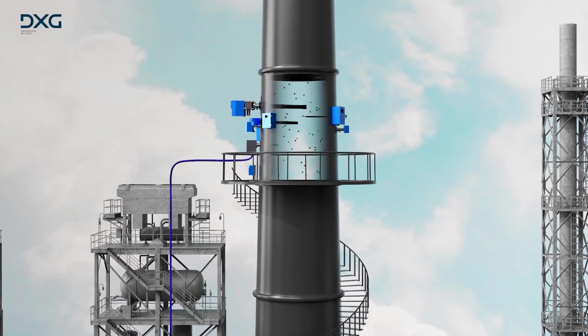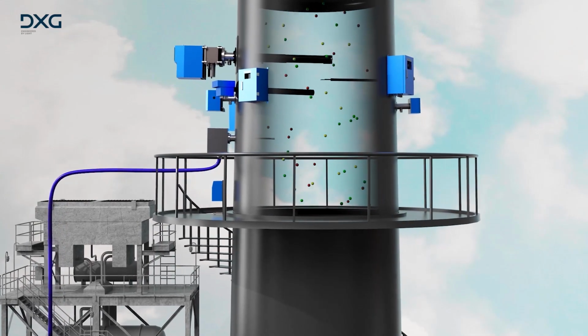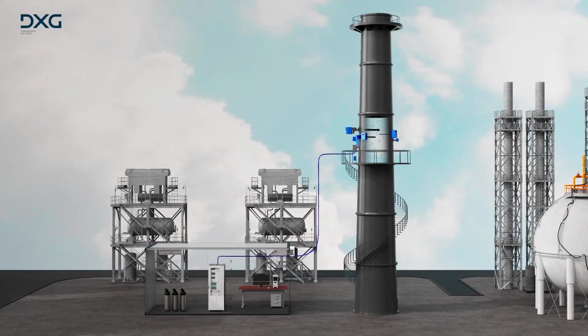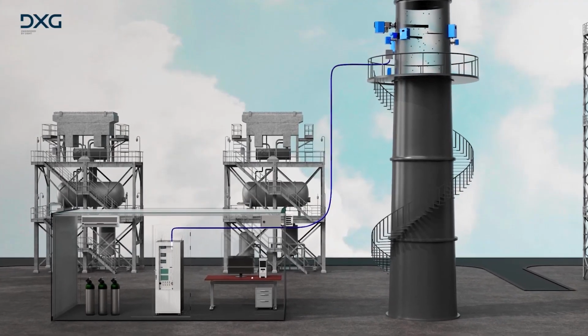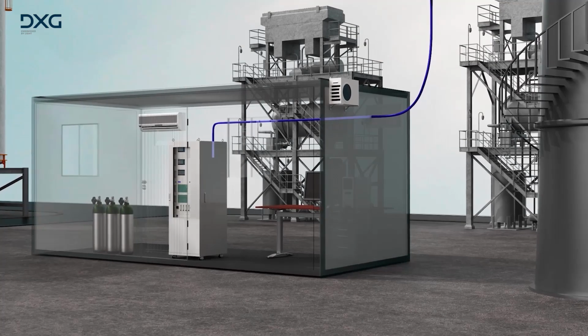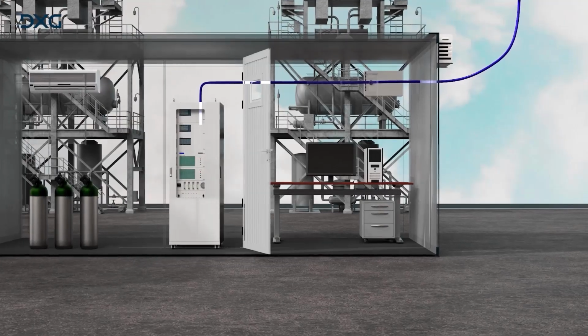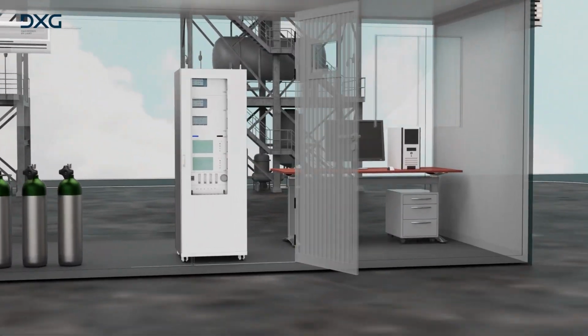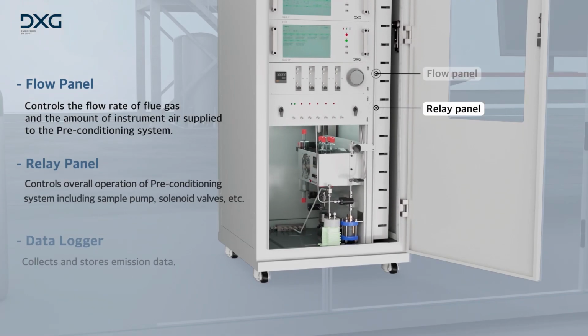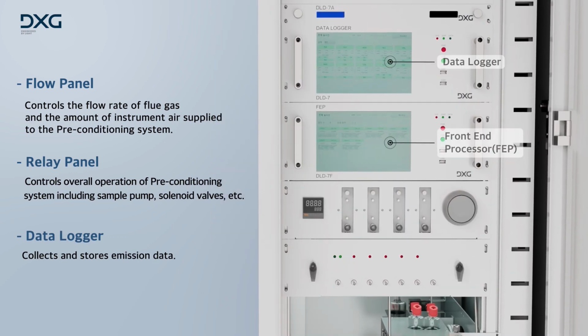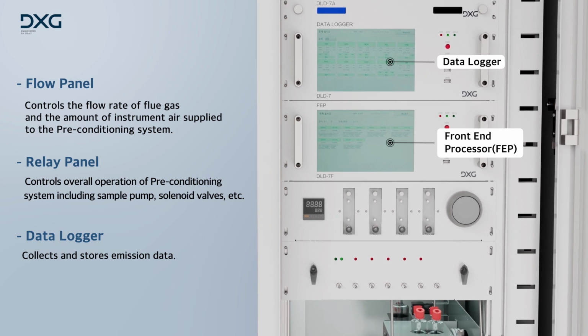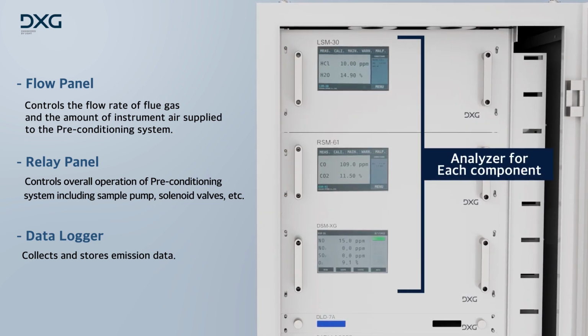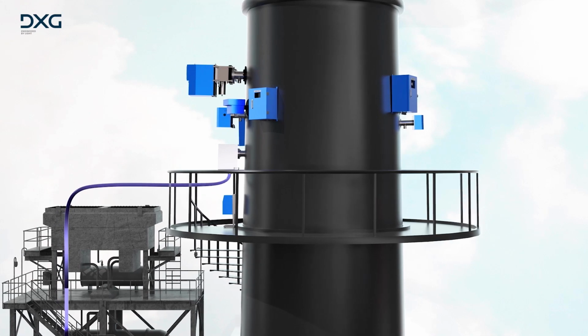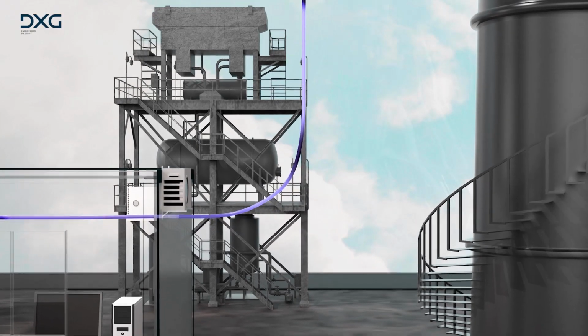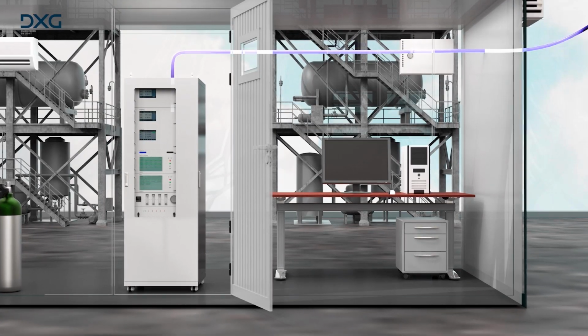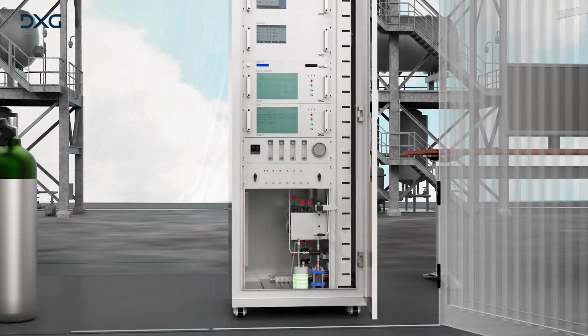In the Extractive type, also referred to as the sampling type, a sample probe and a sample pump are used to extract a gas sample from inside a chimney, which is then sent to an analysis system located in an easily accessible location for conditioning and measurement. The Extractive type consists of a conditioning system, relay panel, flow panel, data acquisition device, data logger, and analyzers for each measured component. As part of the Extractive type measuring method, gas is sampled first by a sample probe, then sent to the analysis system through a heated line kept at a constant high temperature.